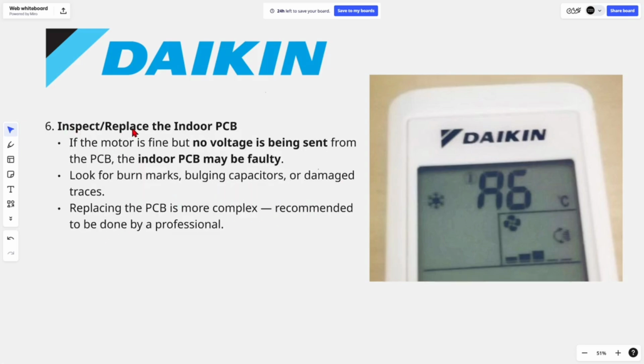Step 6, inspect or replace the indoor PCB. If the motor is fine but no voltage is being sent from the PCB, the indoor PCB may be faulty. Look for burn marks, bulging capacitors or damaged traces. Replacing the PCB is more complex and is recommended to be done by a professional.